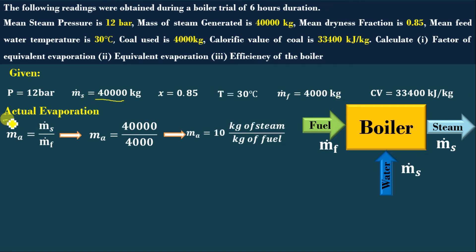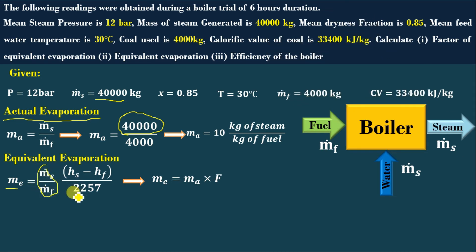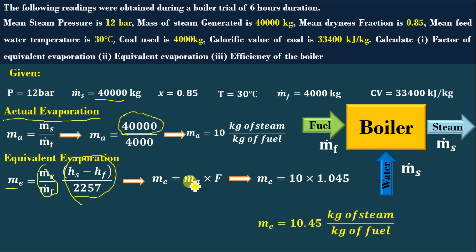As mentioned, actual evaporation alone does not give an effective comparison for the boiler because the outlet steam condition differs — it may be wet steam, dry steam, or superheated steam, and the MS value will vary accordingly. To find the equivalent evaporation Me, we take actual evaporation MA multiplied by the factor of evaporation F. Substituting: Me = 10 × 1.045 = 10.45 kg of steam per kg of fuel. You can see that equivalent evaporation is always greater than actual evaporation when the factor of evaporation exceeds 1.